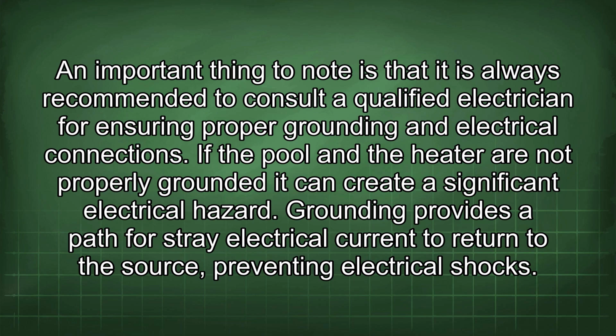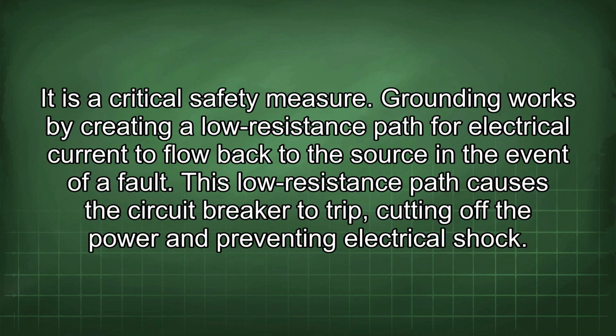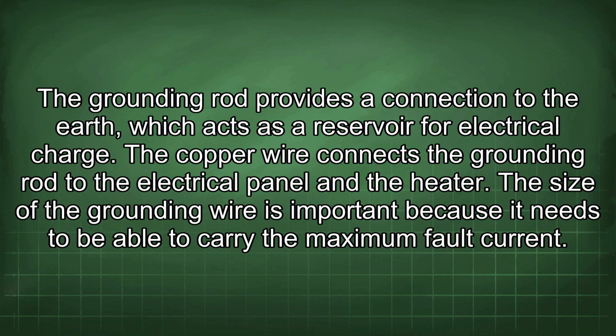Grounding provides a path for stray electrical current to return to the source, preventing electrical shocks. It is a critical safety measure. Grounding works by creating a low resistance path for electrical current to flow back to the source in the event of a fault. This low resistance path causes the circuit breaker to trip, cutting off the power and preventing electrical shock. The grounding rod provides a connection to the earth, which acts as a reservoir for electrical charge.